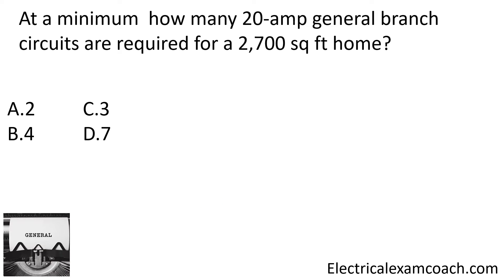At a minimum, how many 20 amp general branch circuits are required for a 2,700 square foot home? Your question may not say 'general' — it may say 'for lighting and receptacles.' But usually if they give you the square feet, that's the red flag that you're calculating the general branch circuits. The first step is to take our 2,700 square feet and multiply it by 3 VAs per square foot, like we've learned previously in the program. That's going to end up with 8,100 VAs.